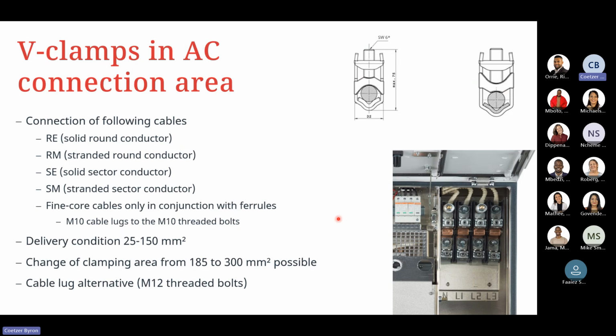So you will have V clamps in the AC connection area. You can use solid round conductor, stranded round conductor, solid sector conductor cable, as well as stranded sector conductor cables, as well as fine core cables, only in conjunction with, for example, bootlace ferrules and using an M10 cable lug on the threaded bolts.